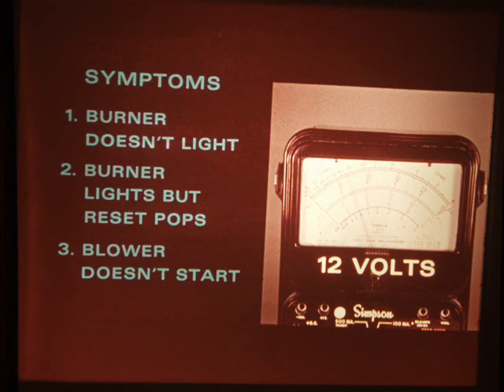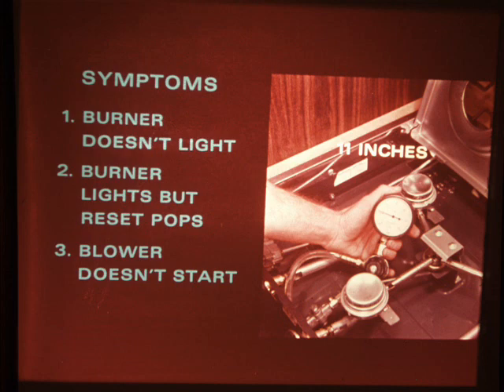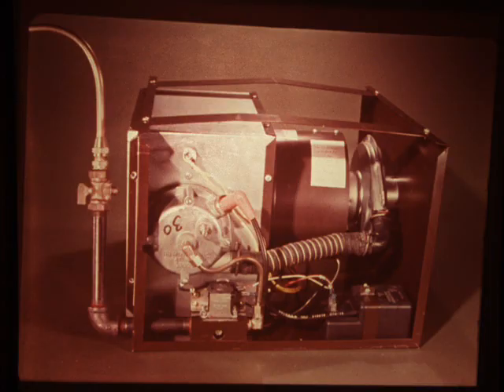However, before you start your trouble diagnosis, there are two external conditions that must be met. First, there must be 12 volts, absolutely no less than 10.5 volts, into the furnace with the furnace on. And there must be 11 inches of gas pressure available, measured at the kitchen range. Here, we're going to demonstrate troubleshooting procedure on the bench so you can see things more clearly. The preliminary checks in each case, however, can be done in the motorhome.